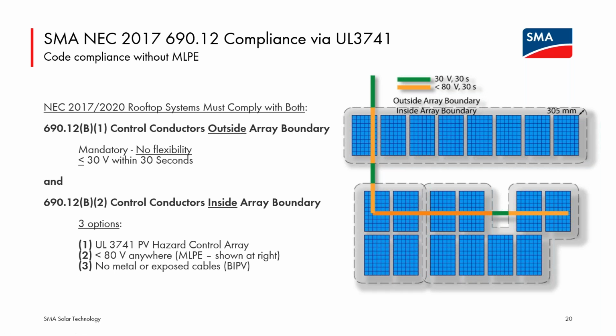There are devices that can comply with that in a very straightforward manner, but that is not the only way that installers can comply. There is the UL 3741 listing. This is a testing procedure that verifies that when rapid shutdown is initiated, shock hazards to first responders, that's firefighters, are within acceptable limits in the array. So it doesn't require a data sheet value that may or may not be tested under conditions for which it is supposed to provide protection. The 3741 testing actually tests under conditions for which this system is supposed to provide firefighter protection.